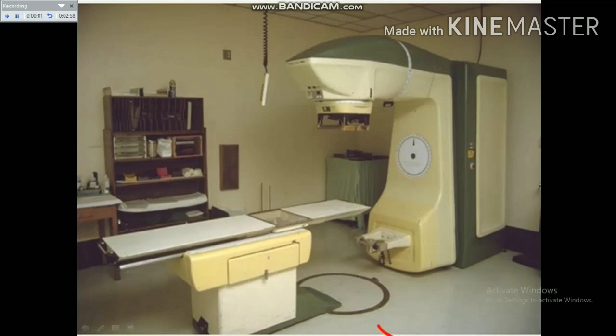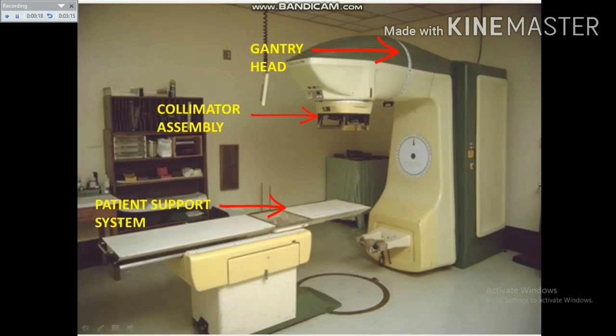In this figure you can see a telecobalt unit. This is the gantry head, this is the collimator assembly, and this is the patient support system or the couch. All three assemblies can be moved, can be rotated from 0 to 360 degrees as per requirement. So these are the main components of a teletherapy machine.